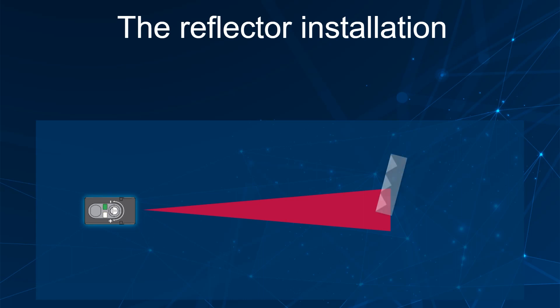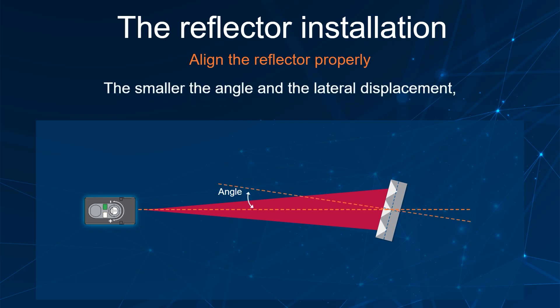The reflector should be installed and aligned properly for best detection performance. It should be installed in front of the sensor regarding the lateral displacement with an acceptable angle. The smaller the angle and the lateral displacement, the higher the sensing distance and the sensing range.